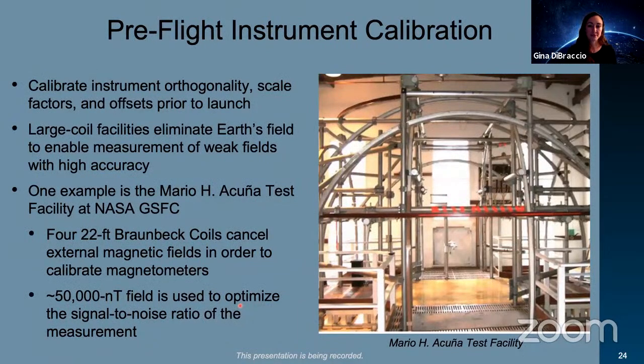So as far as pre-flight instrument calibration is concerned, I mentioned that we want to calibrate the instrument's orthogonality and the scale factor of the instruments, because it's not an absolute measurement that we're getting here. So we need to understand those scale factors, but we also want to understand what the offsets of our measurements are as well prior to launch. And in order to do this, we utilize large coil facilities that are able to eliminate the Earth's field and enable that measurement of the weak field with a high degree of accuracy.